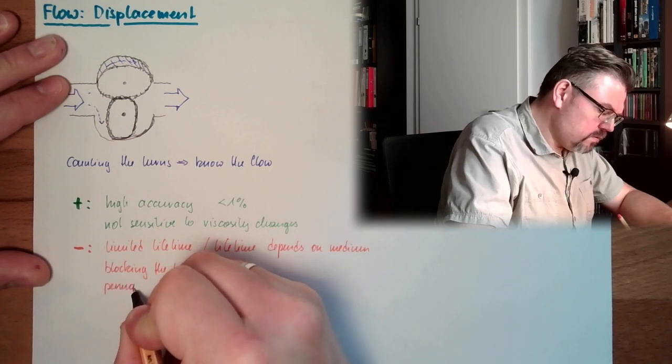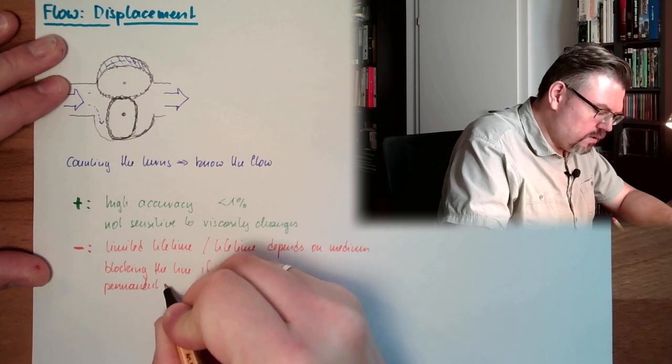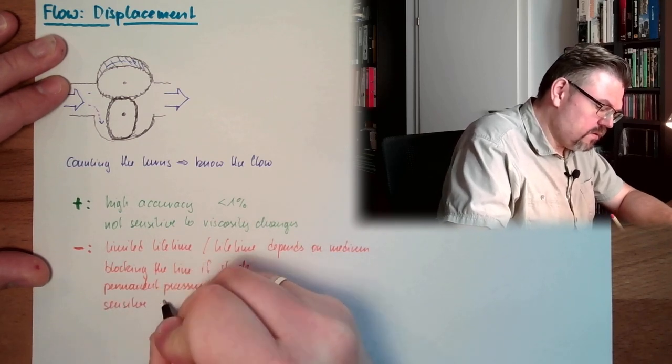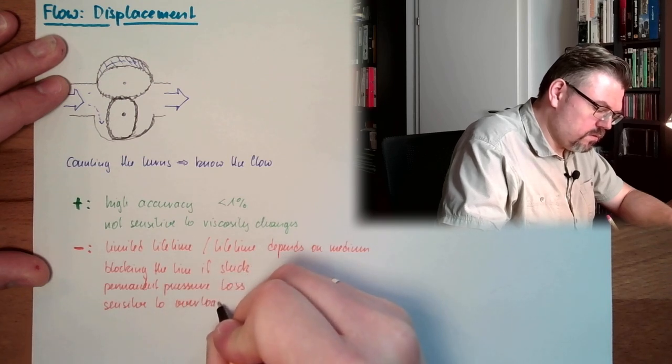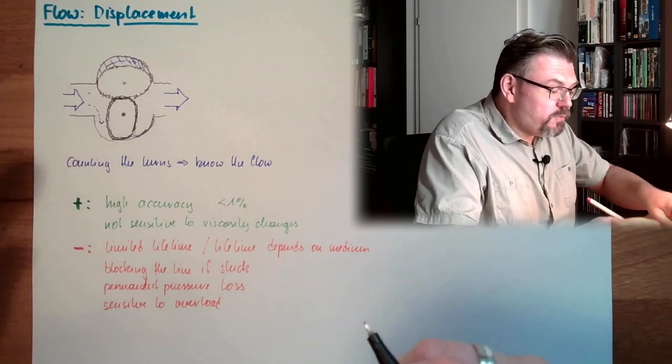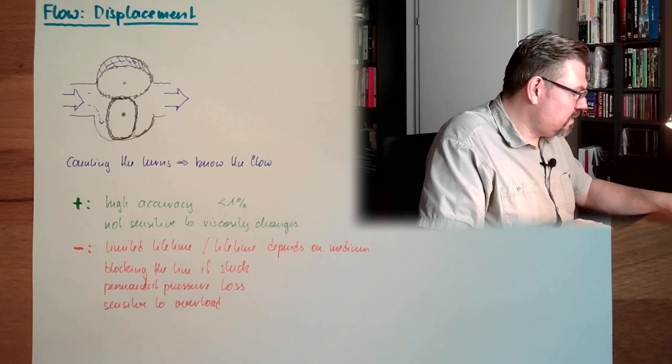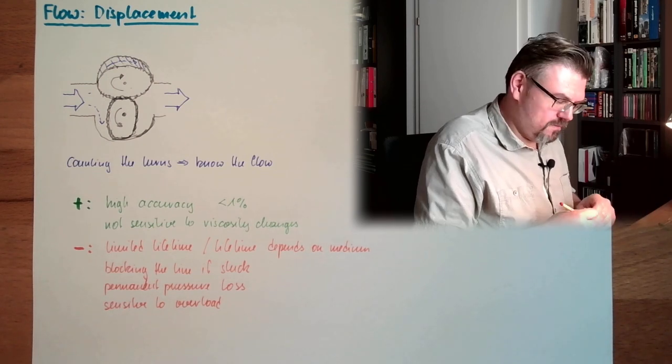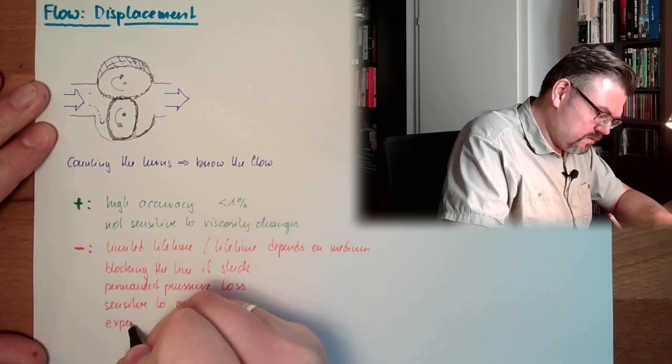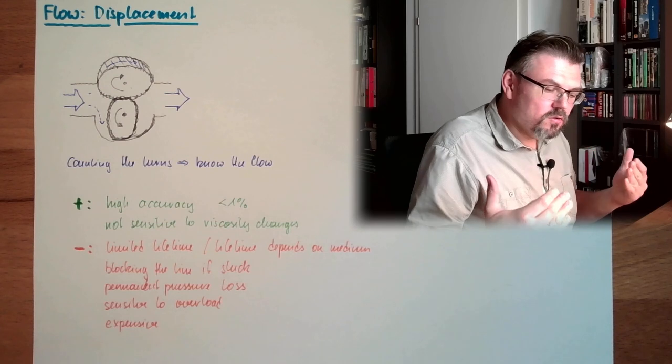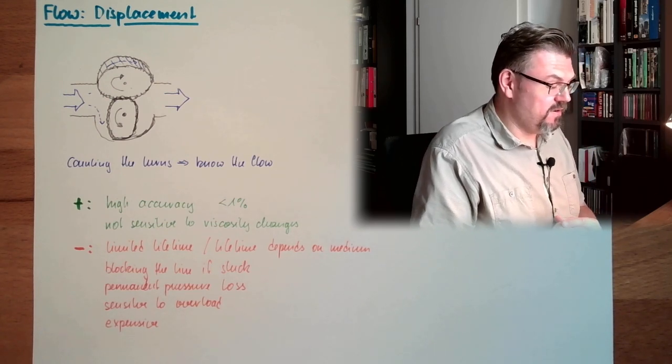We have permanent pressure loss. We are sensitive to overload, overflow in this case. So if there is more water or more liquid rushing through than this thing is designed for, it spins like crazy. Okay, maybe I should also write the spin directions here. And yeah, this is not working long. And we are expensive. High accuracy parts inside. We need high efforts to build it. So we are relatively expensive for this type of flow measurement.